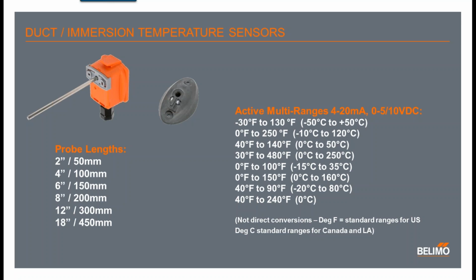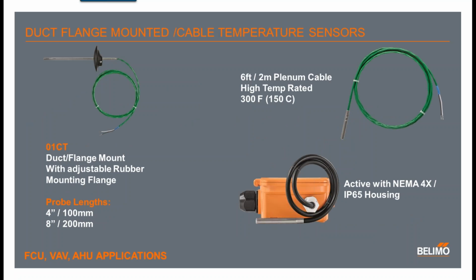The active sensors are available with 4 to 20 milliamp or selectable 0 to 5, 0 to 10 volts. And each active temperature sensor has 8 field selectable ranges in one single device. The ranges can also be jumper selected from degrees Fahrenheit to degrees Celsius to cover all regions. We have duct flange mounted sensors with an adjustable rubber mounting flange for fan coil unit applications, VAV, air handling unit applications. All of our cable sensors come with a high temp rated plenum cable up to 300 degrees Fahrenheit, and the active sensors come complete with the NEMA 4X IP65 housing.